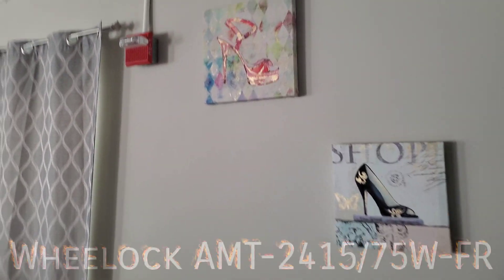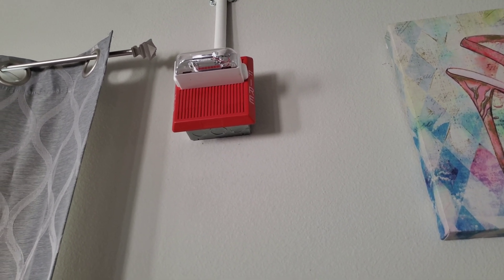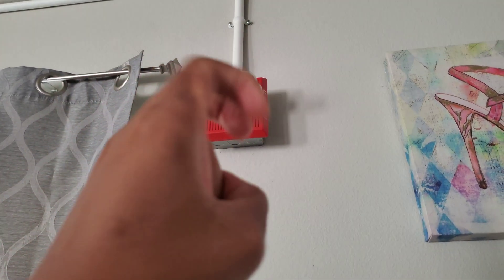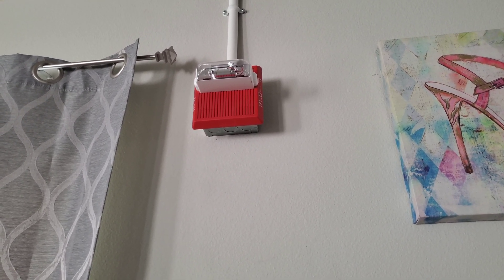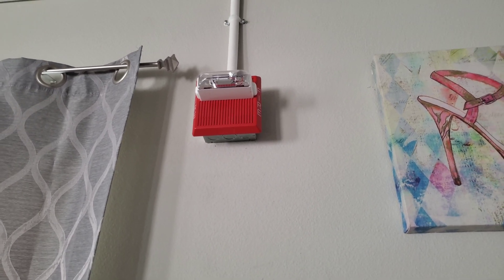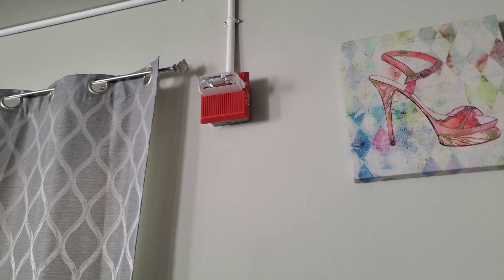Downstairs we have the AMT-24-1575-WFR, a newer generation MT, set on the siren tone. It has three priorities on the back — addressable notification appliances, but not the SLC-type addressable. It's still a conventional alarm that just has three priorities, so you can use one for fire, security, or whatever. It's a fixed 15/75 candela strobe and is an RSS strobe, so it is synchronizable.